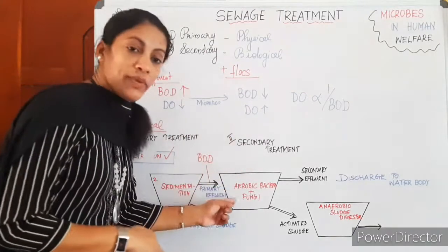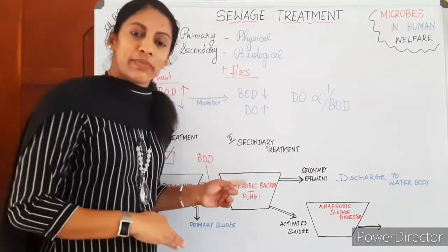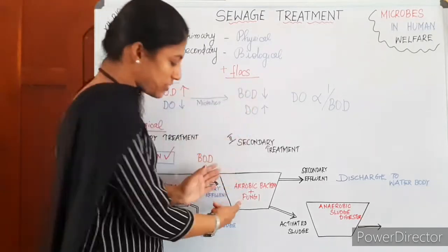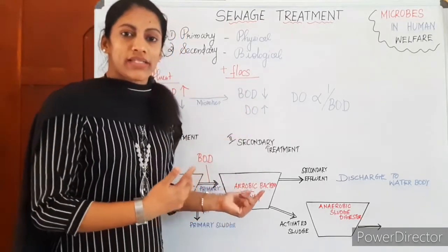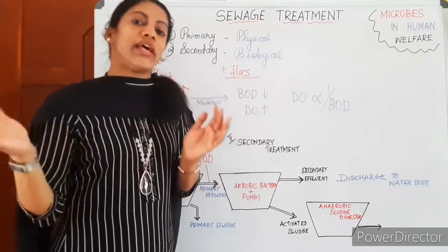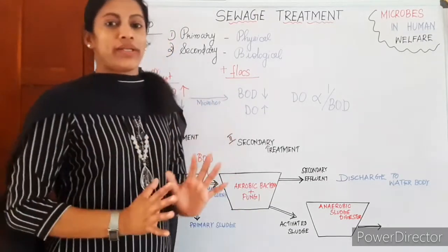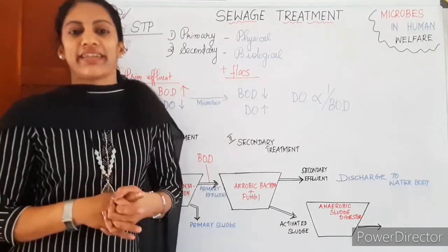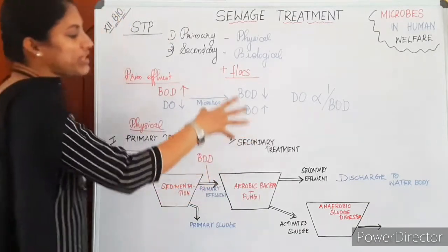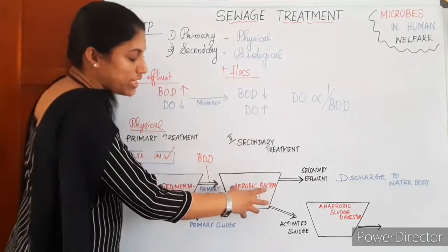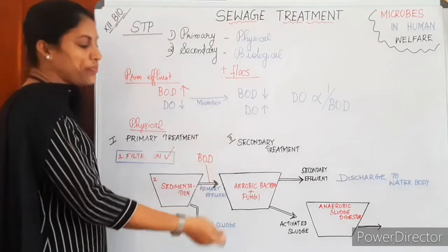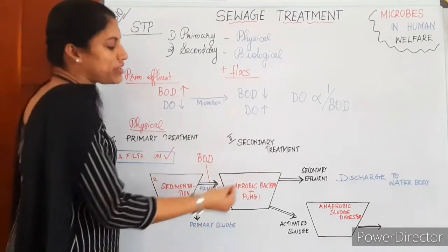This is what is taking place in the secondary treatment tank, and there is a frequent aeration system. Here, there are aerobic bacteria inside, and an agitator system pumps air frequently. Only then do they get proper growth and proper degradation. The BOD can be tested gradually by collecting a sample, and it can be done with a simple titration.